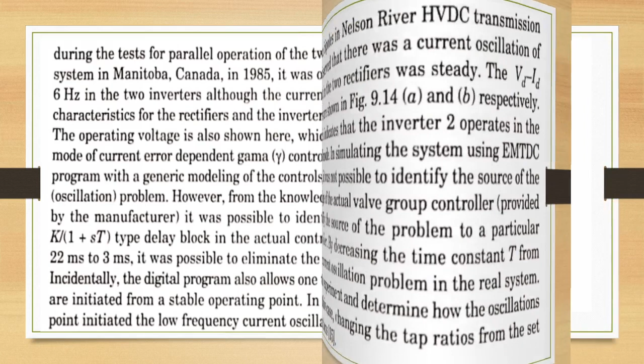Vd, Id characteristics for rectifiers and inverters are shown in these figures A and B. Operating voltage is also shown here, which indicates that the inverter 2 operates in the mode of current error dependent gamma control mode. In simulating the system using the EMTDC program with a generic modeling of the controls, it was not possible to identify the source of the problem.